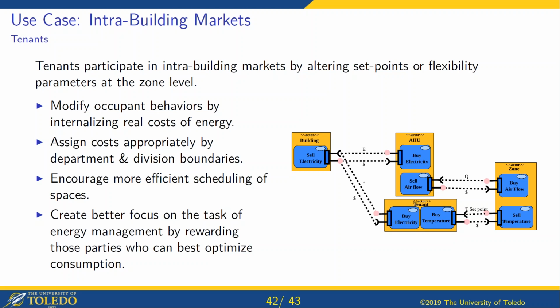So Dave, this is a good time for me to interject. Going back to the beginning where I talked about the campus utilization index, UT already has a very flat profile, and we're still implementing more LED on campus and progressively tightening up the controls. It's behind the scenes, so occupants don't really see it, but the campus sees robust savings on the supply side and the demand side. With VOLTTRON on top of it, someday I can see all automation companies having something like this built into their programs. In this case, trading zone to zone can help us get to a lower EUI, so we can break 100, which would be the magic number for us, or if you're at 120 or 130, it could help you accelerate even further.